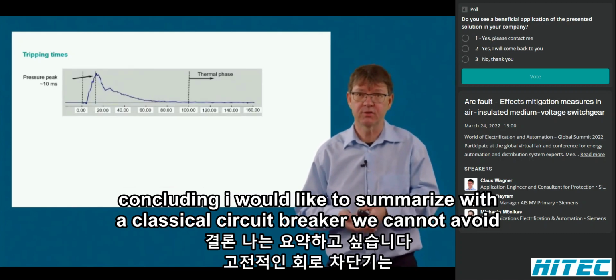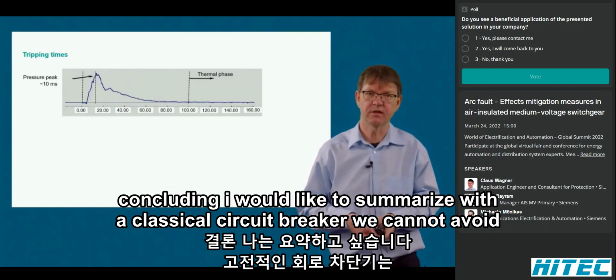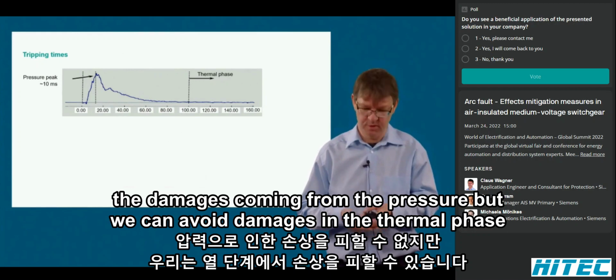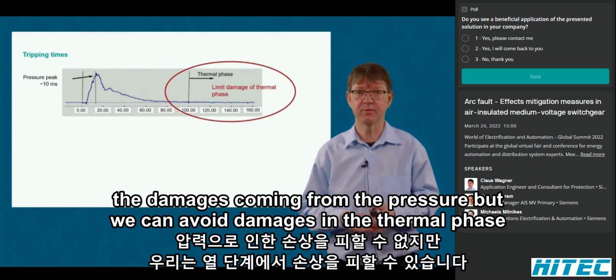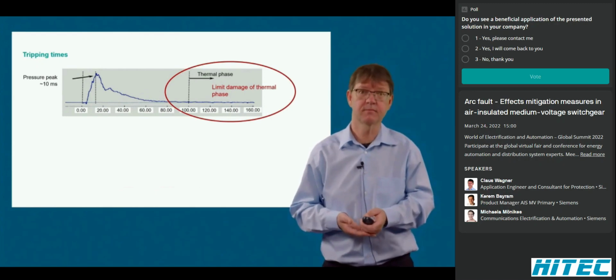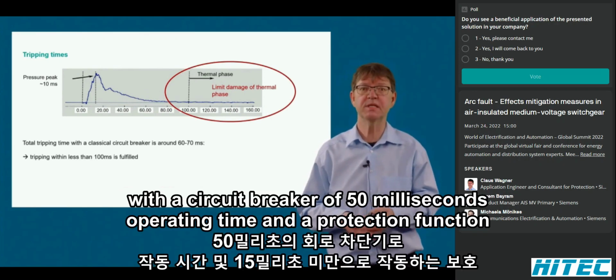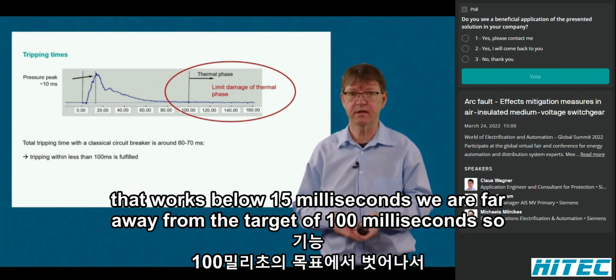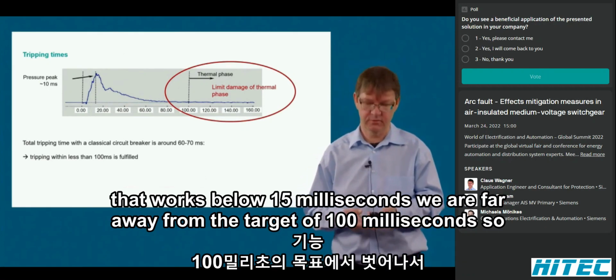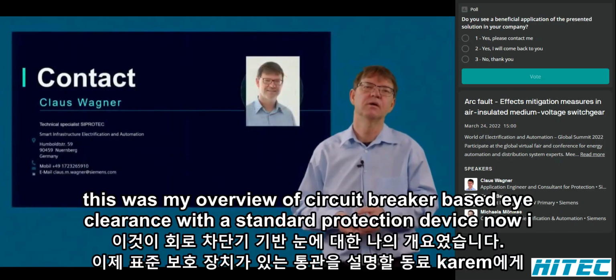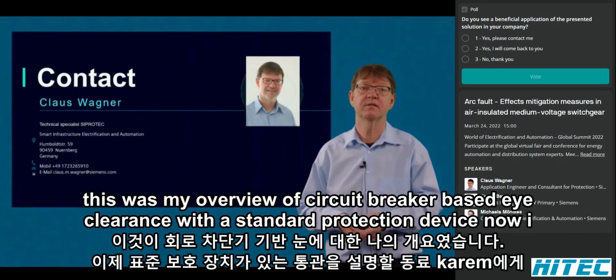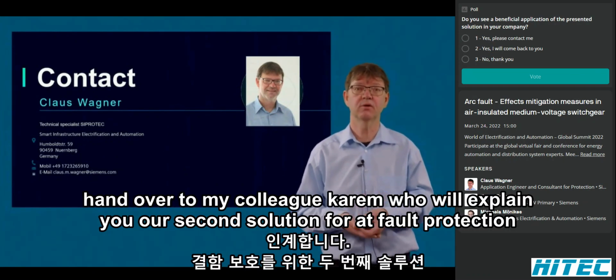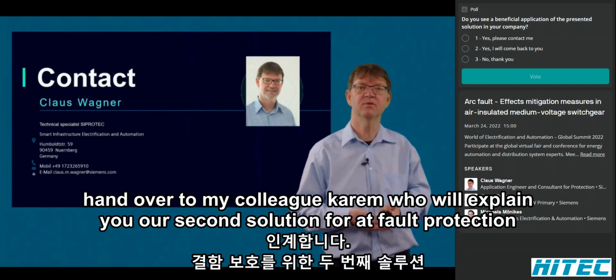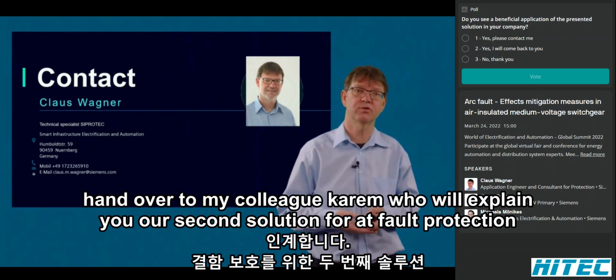Concluding, I would like to summarize. With a classical circuit breaker, we cannot avoid the damages coming from the pressure, but we can avoid damages in the thermal phase. With a circuit breaker of 50 milliseconds operating time and a protection function that works below 15 milliseconds, we are far away from the target of 100 milliseconds. So this was my overview of circuit breaker-based arc clearance with a standard protection device. Now I hand over to my colleague Kerem, who will explain you our second solution for arc fault protection.